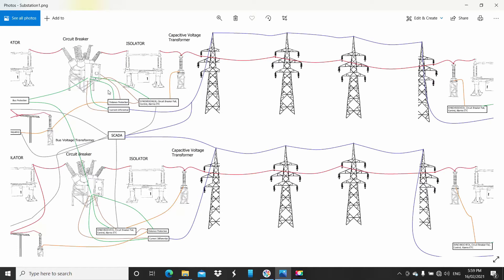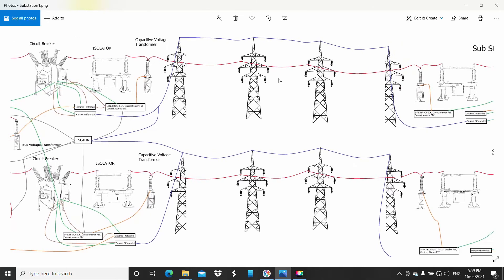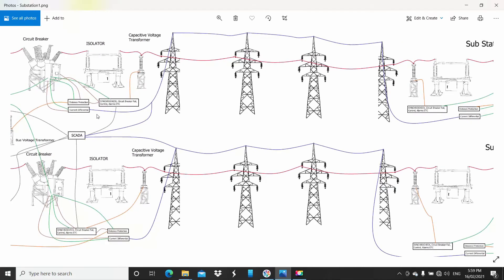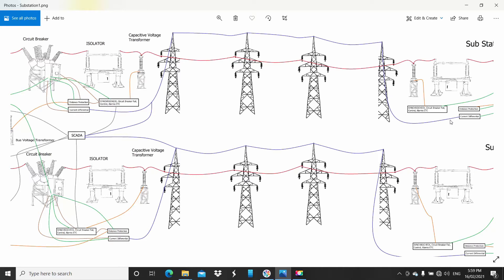I've got a current differential. You can see it's also got a CT into it, an action coming out of it, and the blue is going to represent communications. This current differential relay is communication-assisted. That means I have a fiber optic connection across the top of the transmission lines to the other side. What it's doing is looking at the current going in and the current going out. If they don't equal, it means there's a bypass, there's a fault, and it'll trip.